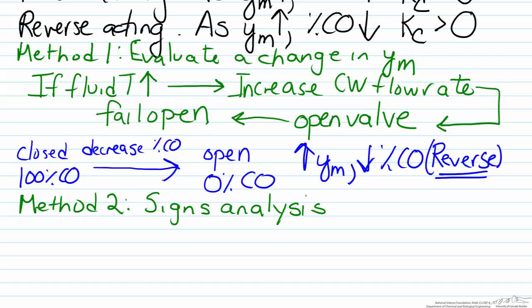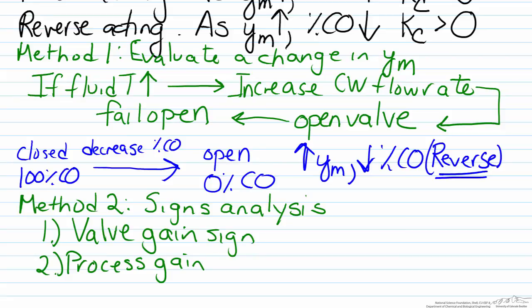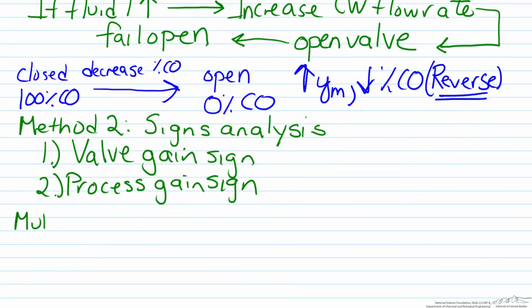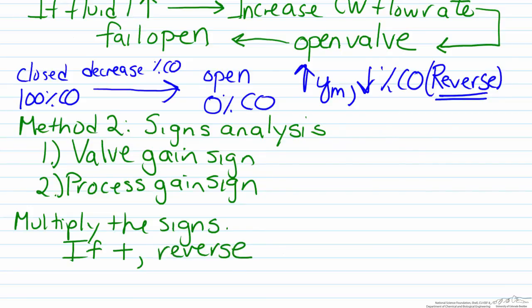We are interested in the sign of two things. The first is the sign of the valve gain, and the second is the sign of the process gain. What we do in this method is we multiply the signs of the valve gain and the process gain. If this multiplication leads to a positive, then the controller will be reverse acting. Similarly if the signs multiplied together are negative, we would select a direct acting controller.